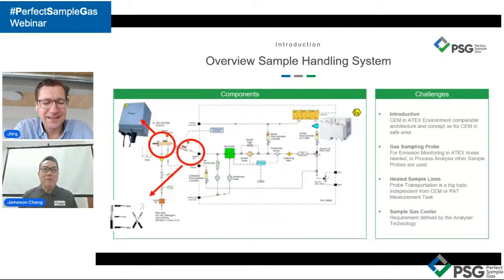Therefore, it really needs a bit of knowledge. That's why we have probes designed this way. The heated line has to be connected in certain ways and at certain temperatures, for example, the heated sample line, we call it the analytical heated sample line. The word analytical actually covers a lot of other meanings. We have taken into consideration the losses, the transportation, the absorptions.